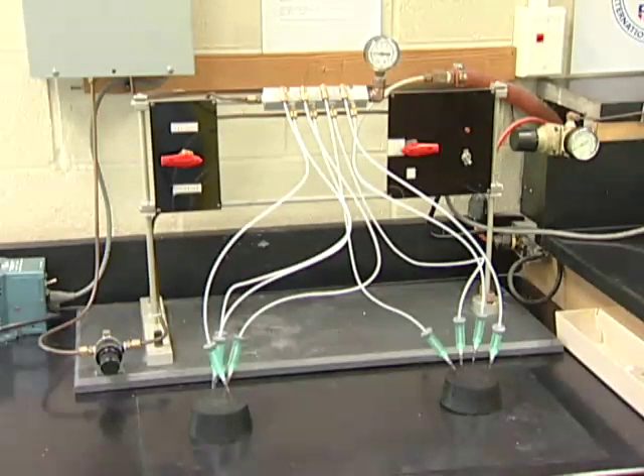The gassing lines and connections must be more robust than for a low pressure gassing station. That is, the tubing is often metal or polyethylene. Connections are made for the most part using compression fittings.